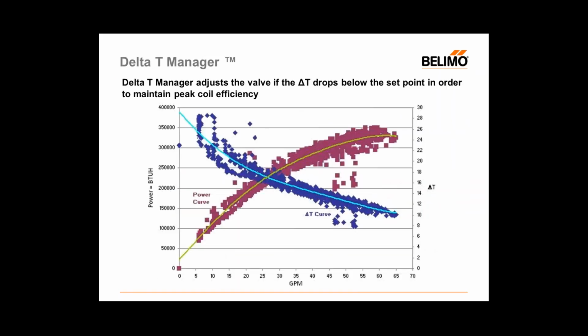So how does the delta T manager work? The delta T manager inside the energy valve essentially monitors the temperature before and after the coil at all times. And as it does that, it's looking for a low limit threshold. So as you program the energy valve, you're going to say this is a 12 degree coil, or we know we can get enough heat transfer for what we need to do at 12 degrees F. And so we're going to set that within delta T manager. And so it will monitor and say, as long as we're above 12 degrees F of delta T, the valve can operate in response to the automation system.